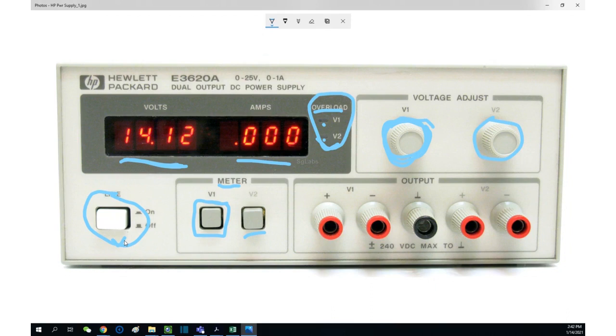If you see overload lights on, then what's the reason? Possibly there's what? Short circuit, which is introducing big current. That big current is introducing overload. This is what generally speaking happens. Obviously you want to turn off the power supply and also check the connection somewhere wrong.